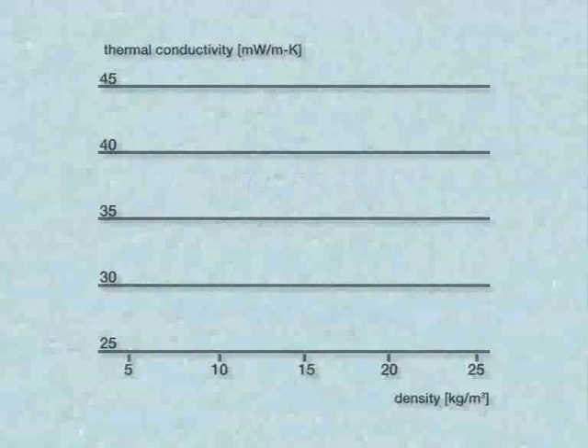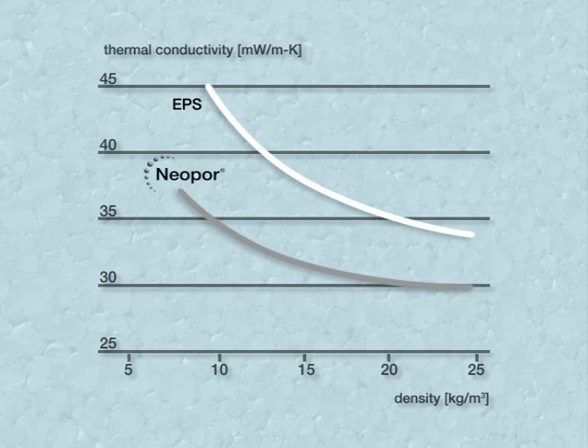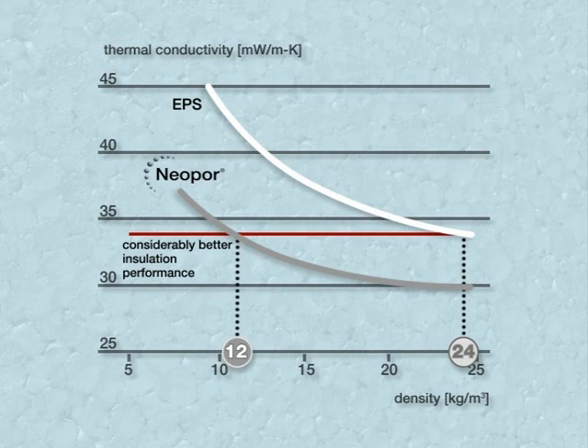The thermal conductivity of insulation materials such as EPS, which contain only air as cell gas, depends largely upon their density. The target is to achieve the lowest possible lambda value — in other words, as little heat as possible should pass through the foam. Thanks to its integrated reflectors, Neopor at its lowest density achieves the same lambda value as standard EPS with twice the density. This means that for the same degree of insulation, a saving is made of up to 50% on raw material usage and thereby also weight.